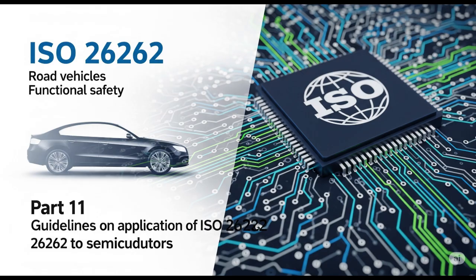Yes, exactly. Specific verification techniques for digital design include HDL simulation, where the hardware design is run in a sophisticated software environment to check its behavior against specifications using test benches. Then there's formal verification, which uses mathematical proof techniques to formally guarantee that certain properties of the design, like this state is never reachable, or this output always follows this input, will always hold true under all possible input conditions. It's like a rigorous mathematical proof in geometry, providing very high confidence for specific critical properties. We also use requirement-driven verification, ensuring every single safety requirement traced down to the hardware level is explicitly verified by one or more test cases.